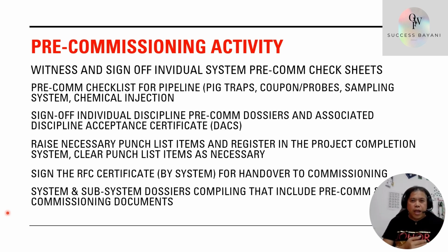Basically we have category A and B. Category A must be closed prior to handing over to the commissioning team. Before giving this to the commissioning team, the dossier must confirm all category A items are closed. The construction contractor prepares the dossier, attaching all test requirements, test reports, FAT testing, dossiers, ITRs, and certificates - all part of the mechanical completion dossier. That is your pre-commissioning activity.